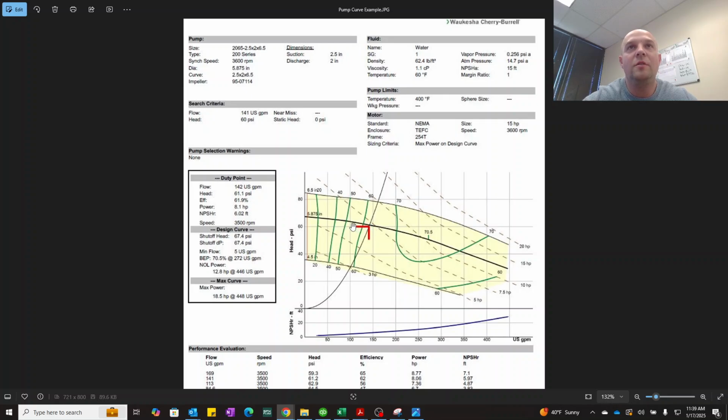If we started going too far left on the curve, okay, we don't want to go too far left or right. As we go too far right, we increase our motor draw and we run the risk of kicking out the motor. As we go too far left, we run the risk of cavitation, okay? One thing we'll see a lot is, especially in applications that are higher pressure and lower flow, you might think like a homogenizer feed application where we really like to use a centrifugal pump.